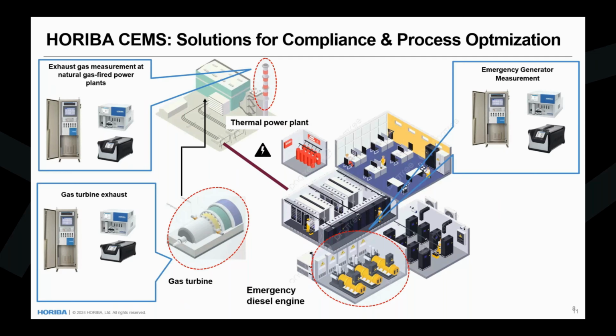Successful monitoring requires more than selecting an analyzer. It also requires designing of sample systems, installation designs, where sample points go, calibration strategy, maintenance planning, and reporting requirements of the site. All these details matter, and they're details that our team brings together, considers, and determines a complete monitoring solution, site-specific, for each one of our customers. It's a process that we go through.